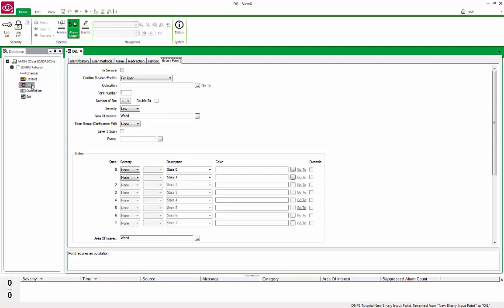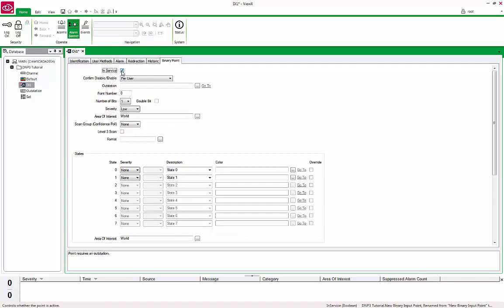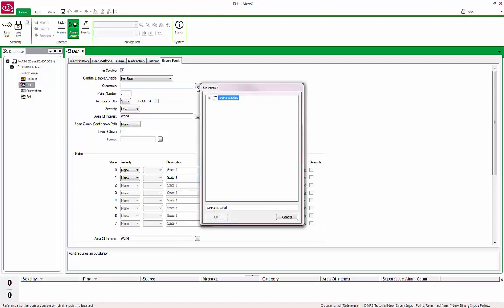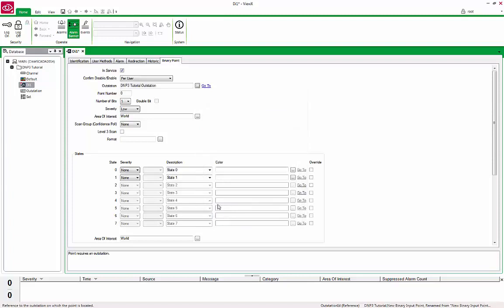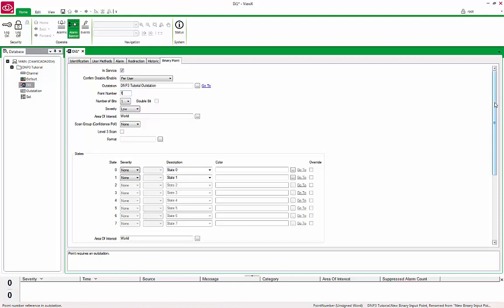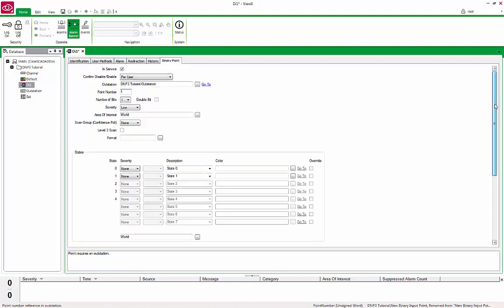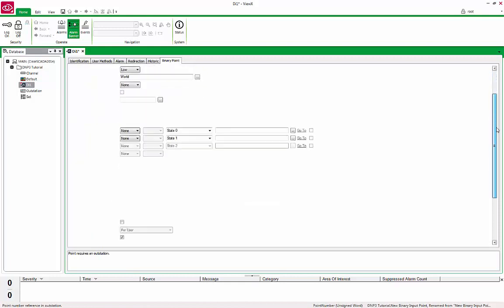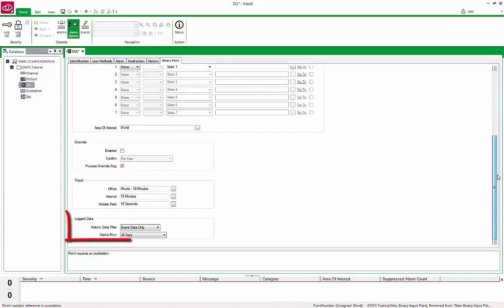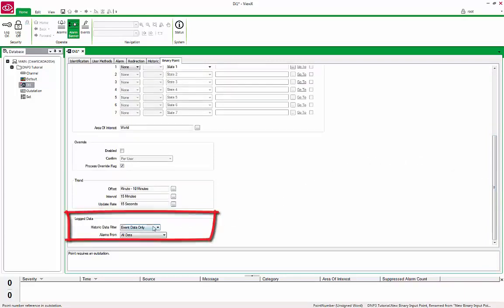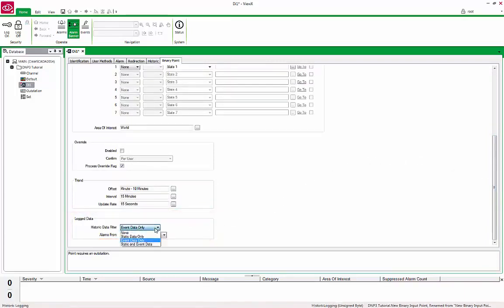Under the Binary Point tab, check the In Service button. Tie the point to the OutStation by browsing to the OutStation we defined earlier. Set the point number to 1, which is the first digital point in our device. Next, scroll down further to Log Data section and under the Historic Data filter, select Static and Event Data from the drop-down list.